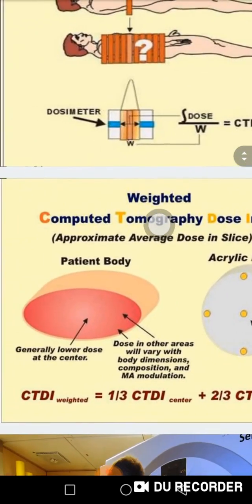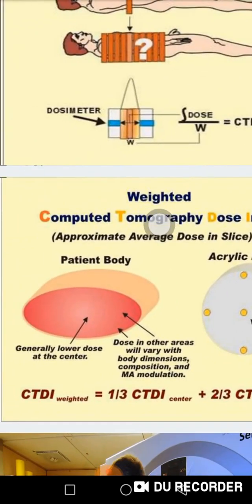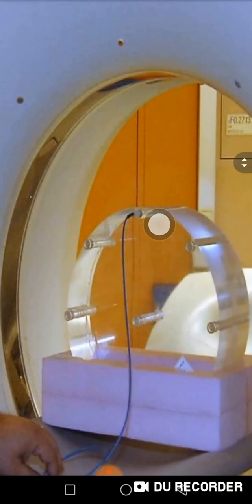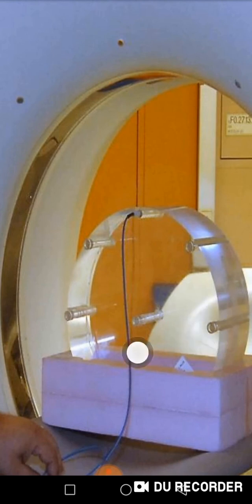I assume a phantom with a group of sections, performing integration for each individual section based on their weights to derive the weighted CTDI index. This is calculated using a phantom — the medical physicist works with this phantom, which has holes: one in the center and holes in the peripheral areas at top, bottom, right, and left, for placing ionization chambers.